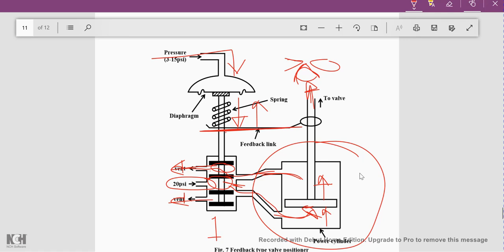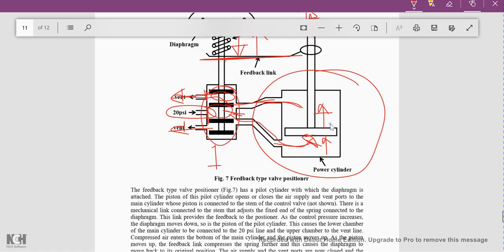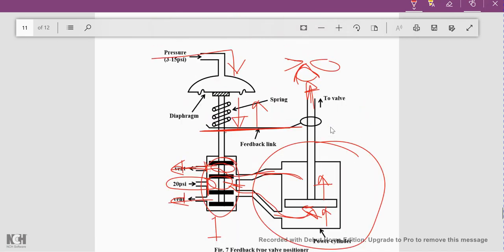The feedback link moves upward with the piston. Whatever expansion in the spring had taken place earlier due to the increase in pressure now goes back to the original position. This moves the piston in the pilot cylinder back to its original position, closing the 20 psi vent and the output vent, thereby maintaining a constant output value. This is how the feedback valve positioner works.